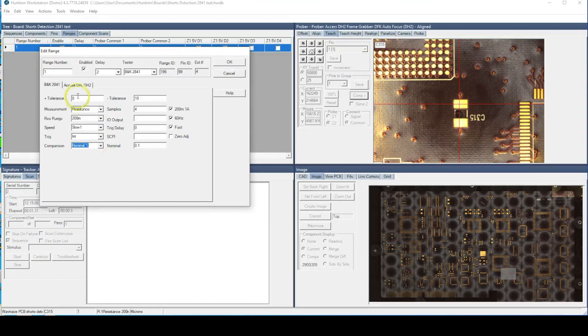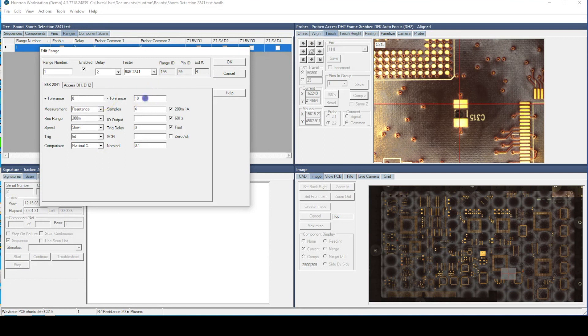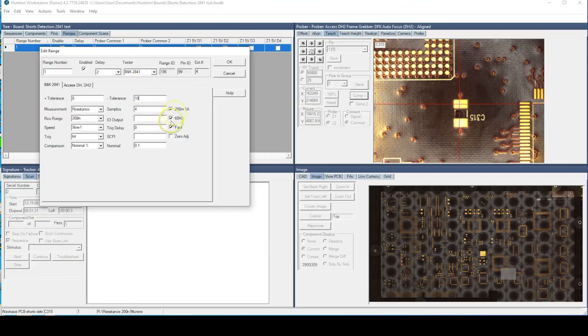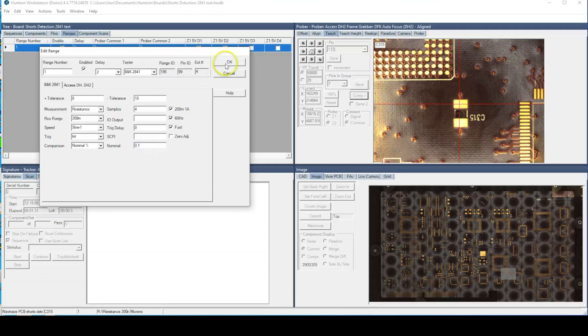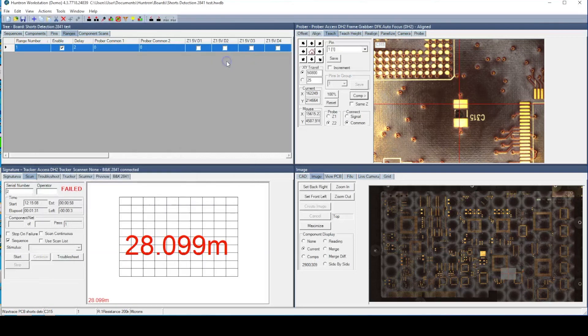The test comparison will use a nominal value with a tolerance set at plus 0 and minus 10%. You can set the number of samples taken and choose to use a high current test. The nominal value is set high at 0.1 ohms to make sure the lowest measurements have the largest difference.